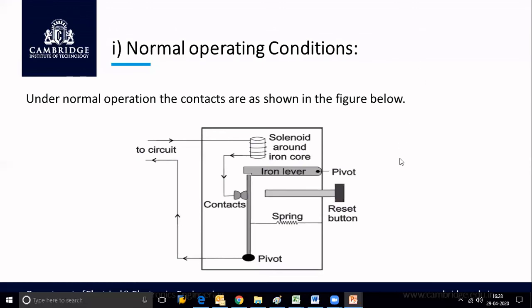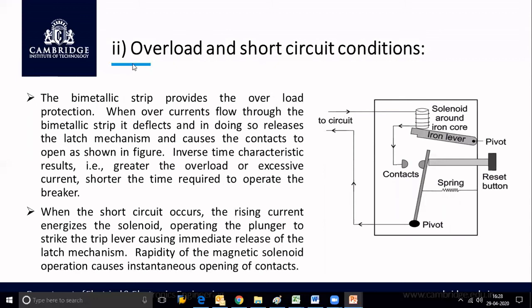Now you can see in the figure how the contacts are under overload or short circuit conditions. The fixed contact stays at its position, and the moving contact has moved like this, which creates a break in the circuit. Usually this is by means of a bimetallic strip, which provides the overload protection. When overcurrent flows through the bimetallic strip, it deflects and in doing so releases the latch mechanism and causes the contacts to open, as shown in the figure.